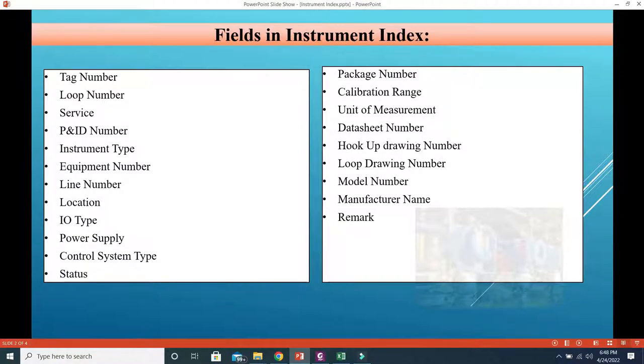So how will you get the tag number and how will you start making the instrument index? First of all, you need to open the P&ID, and before making the instrument index you must know about the P&ID, specifically from the instrumentation side.